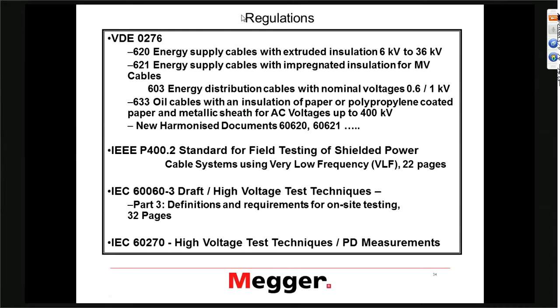In terms of standards: on one side we have in Europe the VDE standards, which are now the CENELEC or IEC standards, and we have IEEE standards — most common in the United States, the 400.2 for VLF testing and the 400.3 for PD testing in the field. There are also IEC standards like IEC 60270, which is also applicable to how to make PD measurements in the field. It's always important to recognize the standards that apply, and when using different methods, to make sure you can compare results from different manufacturers.